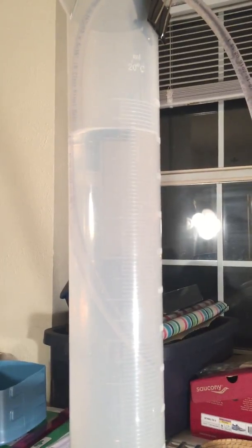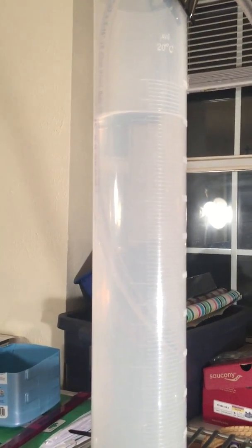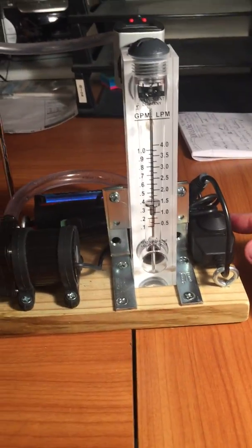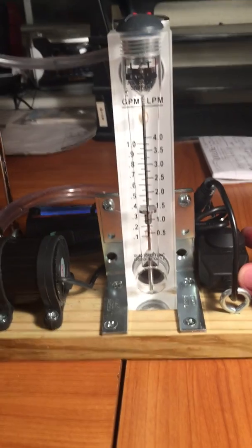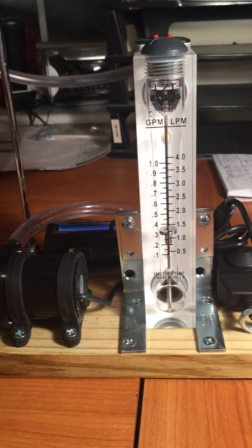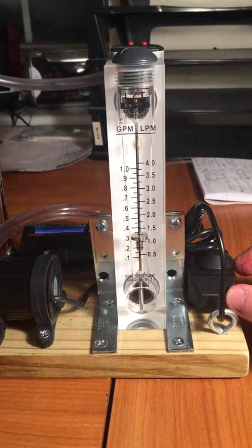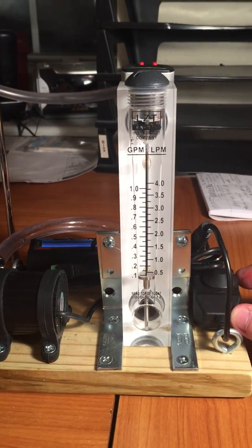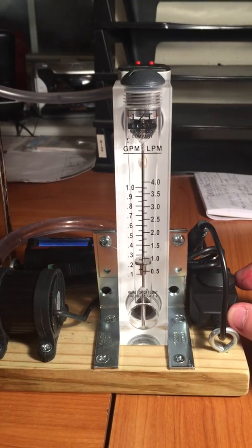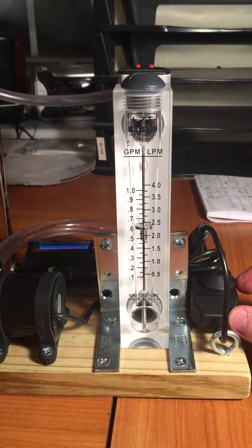So what that means is that the pump is not pumping the water fast enough to maintain steady state. So we're actually losing water in the reservoir. So we need to increase the velocity of the pump until that water level stays fixed. So I'm going to go over here. I'm going to just use this speed controller. I'm going to just keep an eye on the volume flow rate. So what I'm going to do is turn this guy, and you guys will see, the volume flow rate dropped. I don't want that because I'm already losing water. So let's turn this guy the other way, and the volume flow rate will go up.